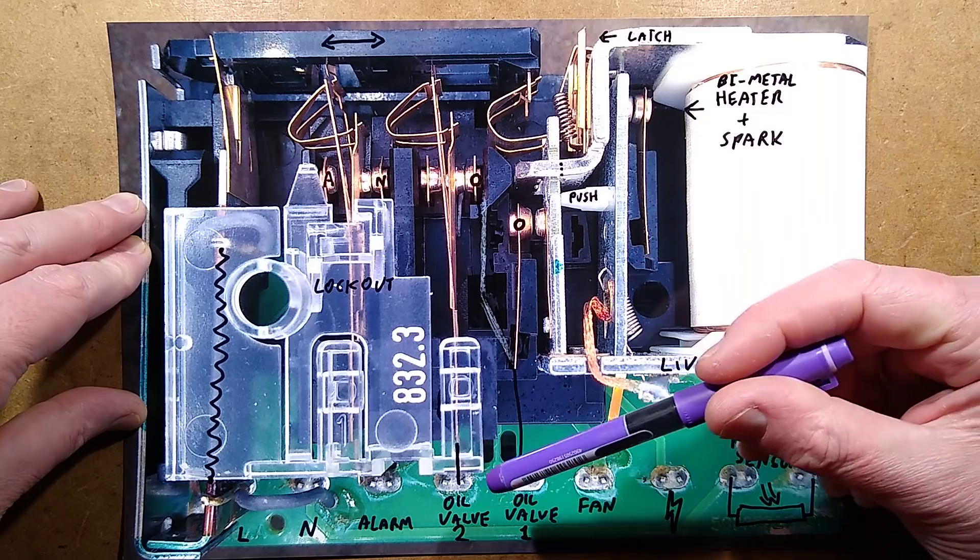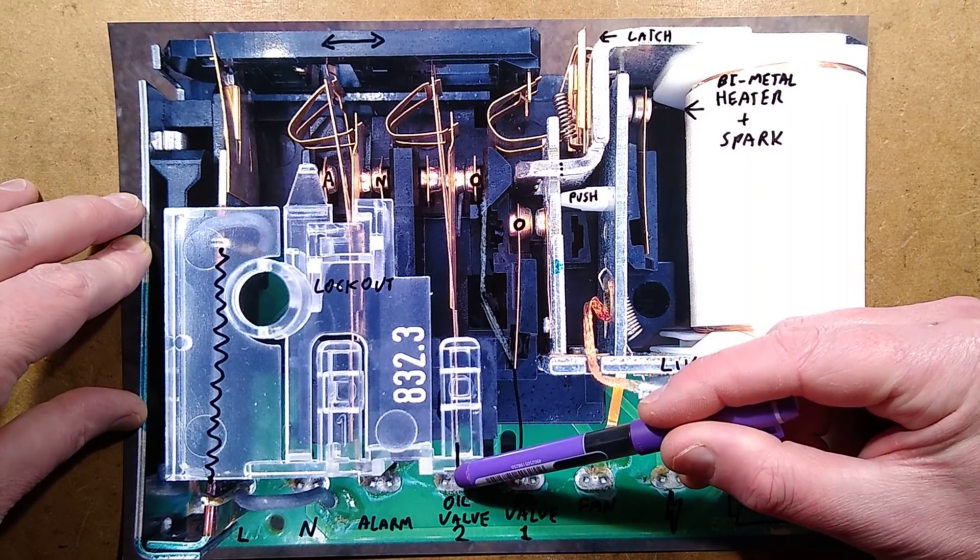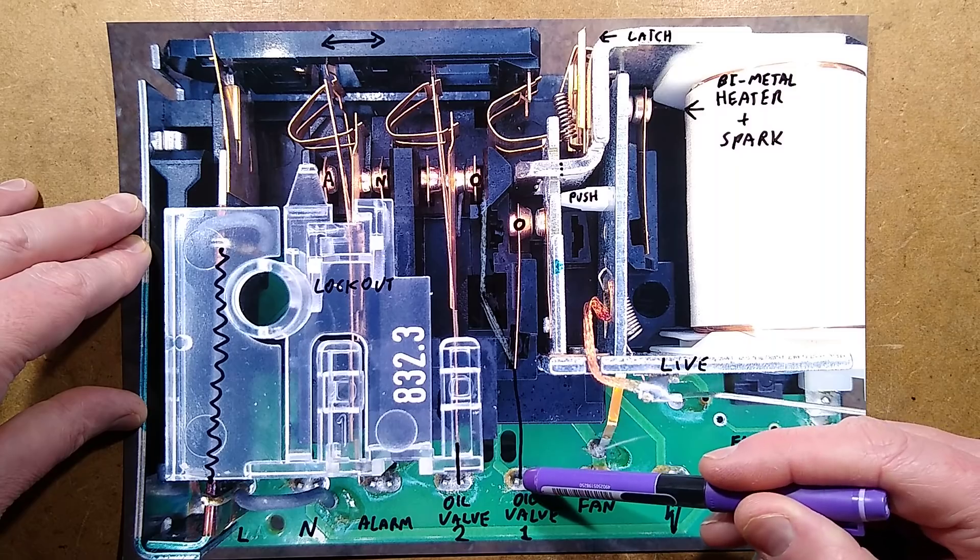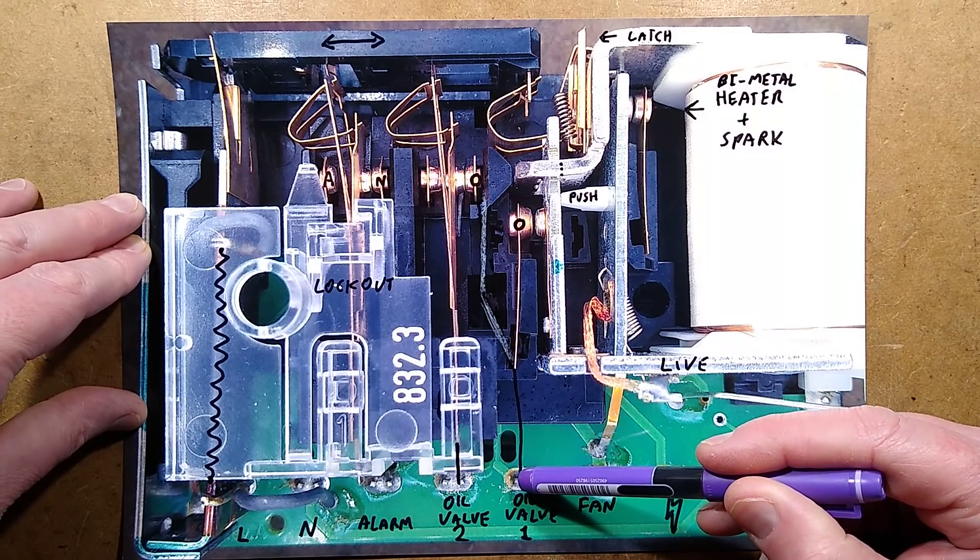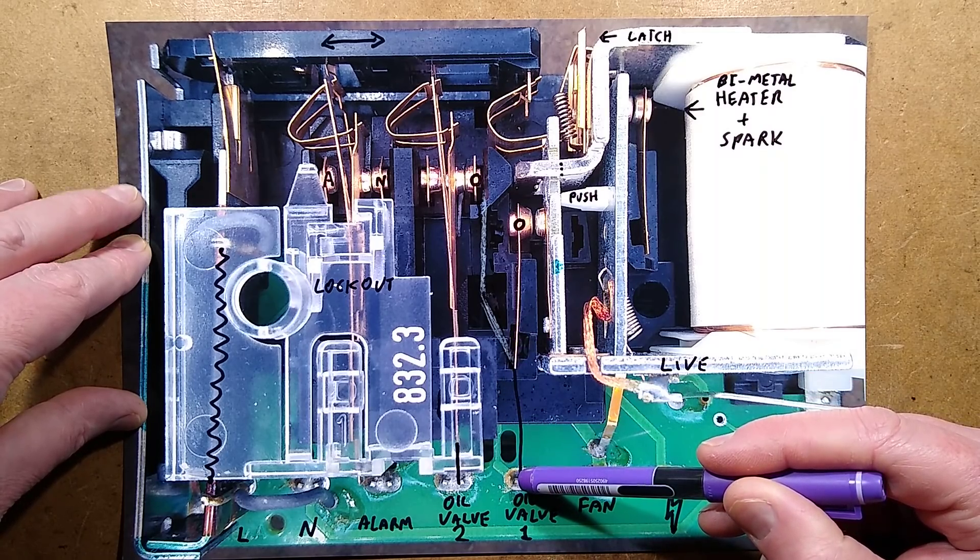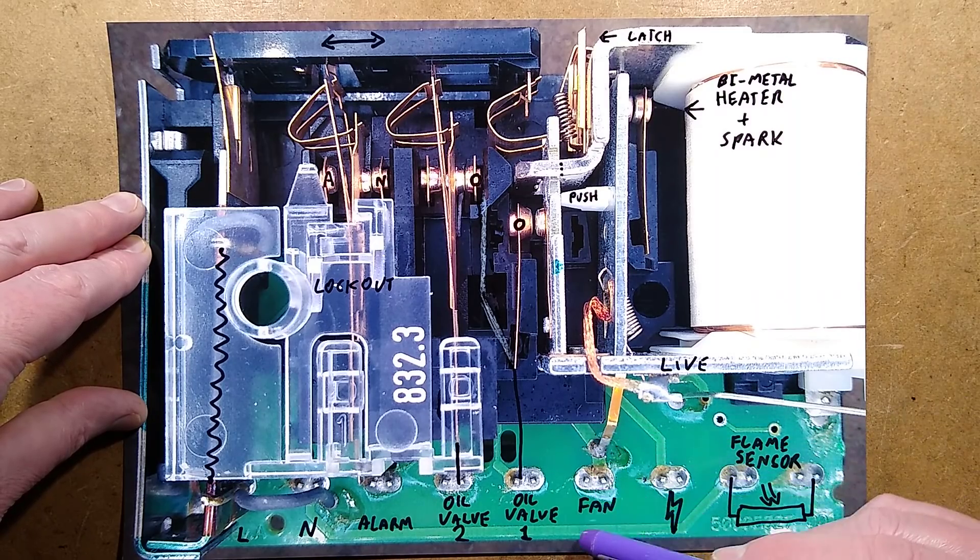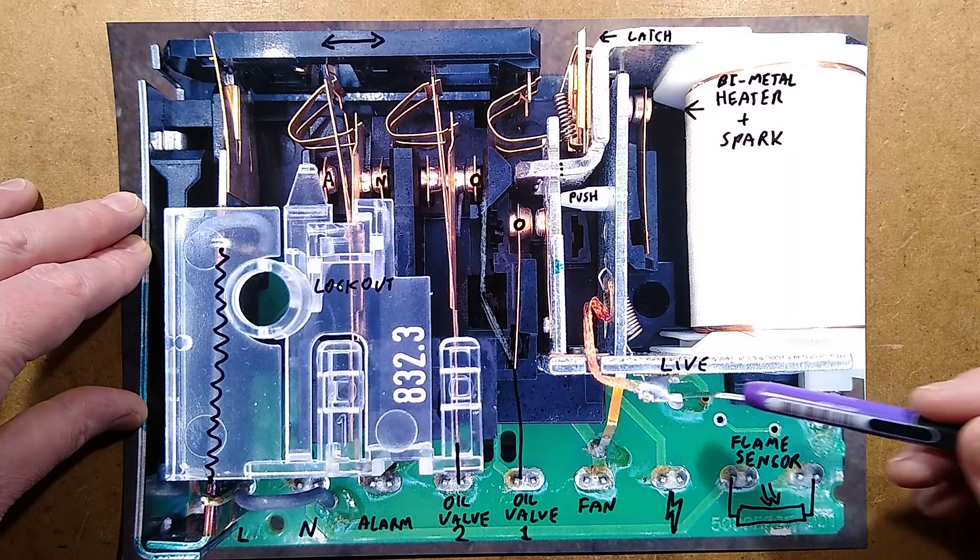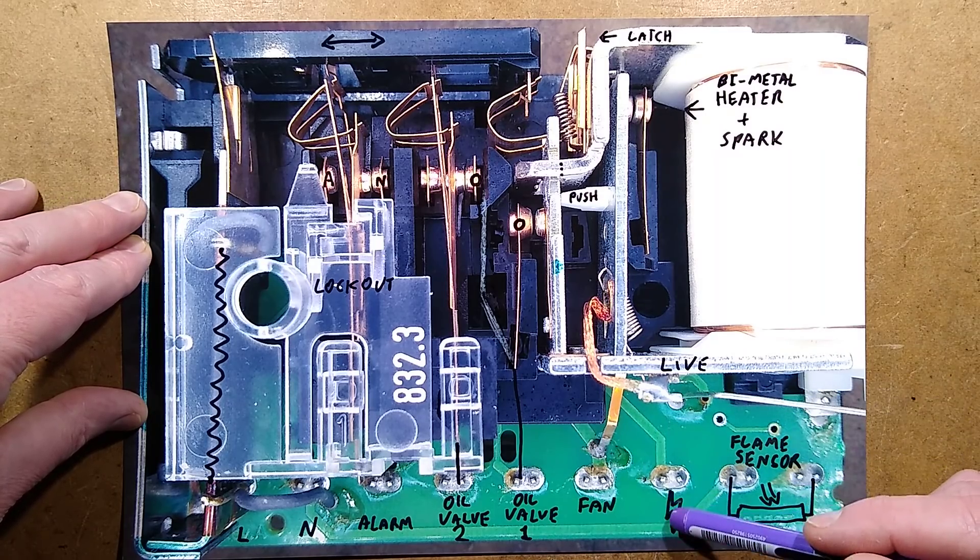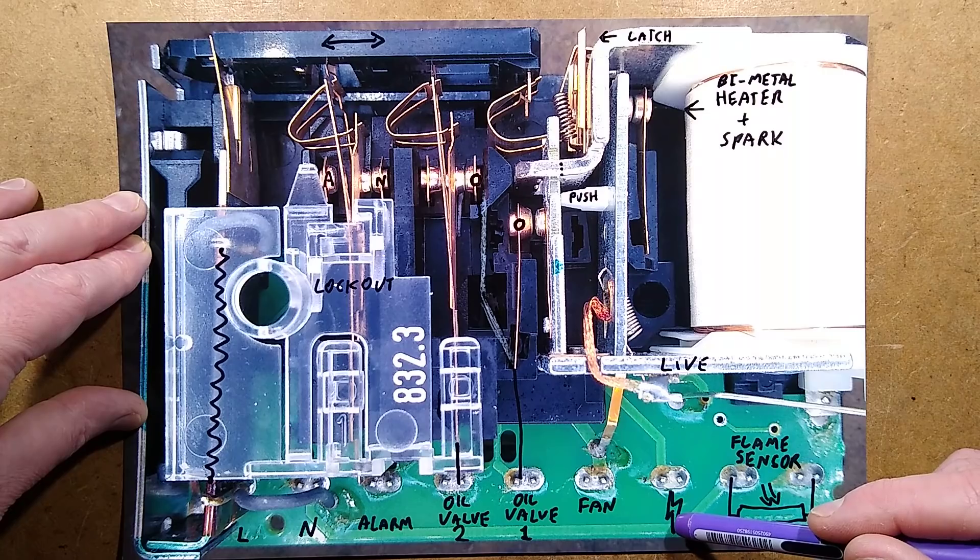Right, the hardest thing about this video is working out where to start. Let's start with the connections at the bottom of the unit. We have live, we have neutral, we have the alarm output which goes live when it goes into alarm mode. We have oil valve 2, which isn't always used, in this case it's not used, and oil valve 1.